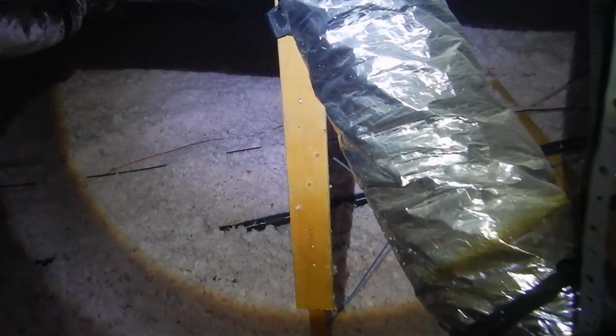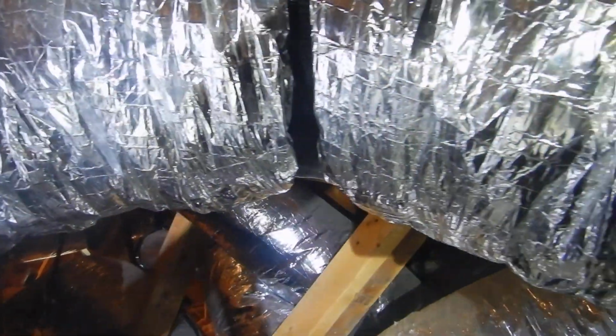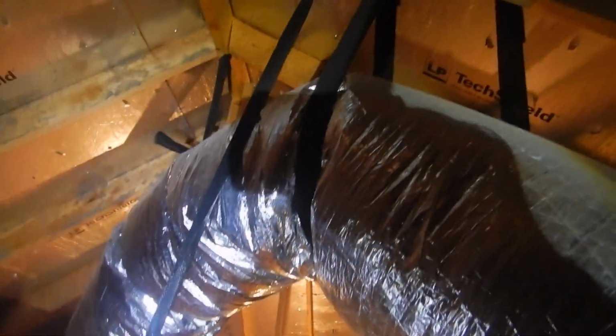But all this nylon webbing is supposed to have saddles underneath it. This will roll up like the elastic on a cheap pair of underwear. And then it starts cutting into your air duct, and constricting your air duct. So we don't want that. We don't want our air duct constricted. We don't want our air duct condensating.